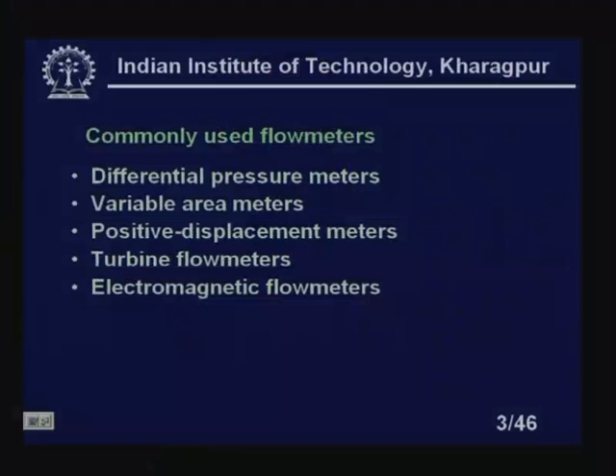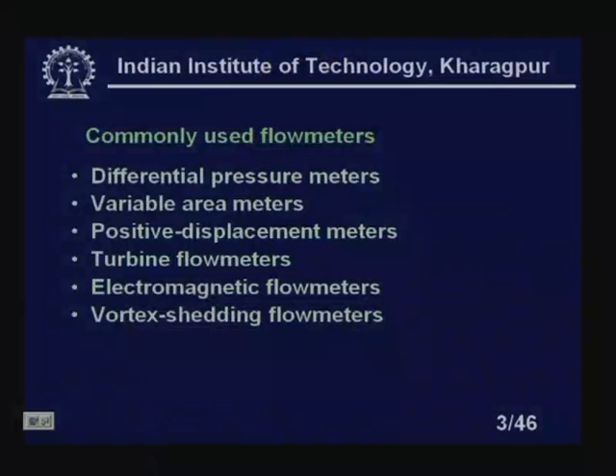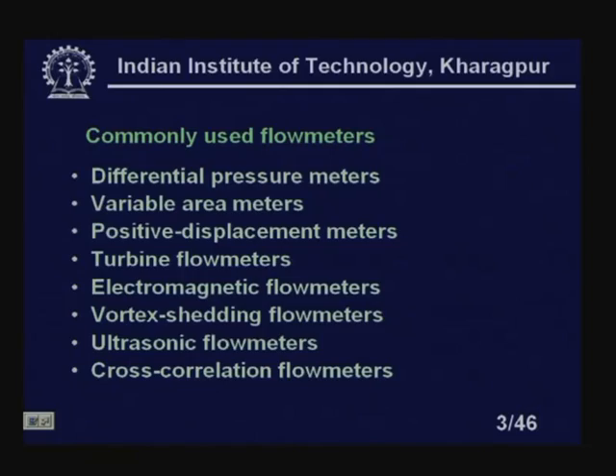We also have turbine flow meters, which give a direct electrical output. We have electromagnetic flow meters, which have advantages because there are no obstructions. We have vortex shedding flow meters, ultrasonic flow meters — which are non-invasive and do not create any pressure loss, unlike differential pressure meters which cause a permanent pressure loss in the pipe. We also have cross-correlation flow meters and laser Doppler flow meters.